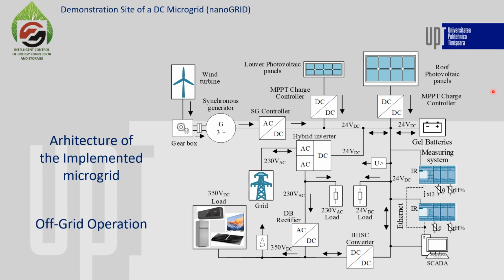The energy storage is composed of four 12 volts, 220 ampere-hours valve regulated lead acid gel batteries, which are especially designed for a residential photovoltaic system. The batteries can store approximately 10 kilowatt hours of electrical energy, which we can say for a usual house is enough for maybe 1 or 2 days, depending on the loads.